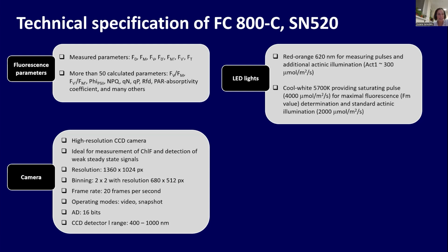So in your device there is a chlorophyll filter that measures the emission band between 690 and 770. This is our optimized filter for chlorophyll fluorescence, but eventually we use the same camera also for bacterial chlorophylls, just using different filters, shifted more to 780, 800. It's not a hyperspectral camera, it's just the sensitivity of the camera. You can use it with different filters. So the same camera we can use with GFP filters, which is in green, 500, 510 nanometers. Here we have the chlorophyll filter. You don't have a filter wheel where you can change the filters, but you can use it up to 1000 with different filters.